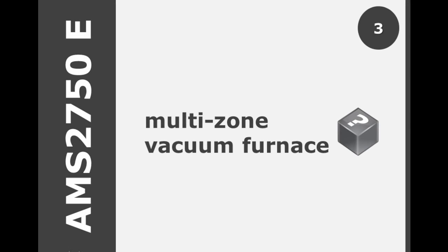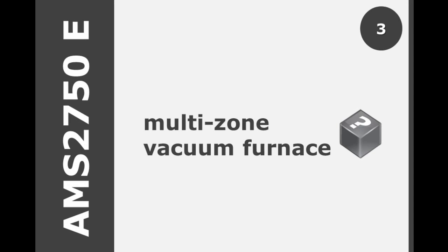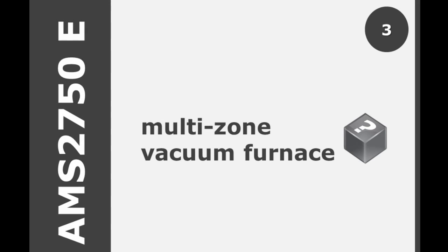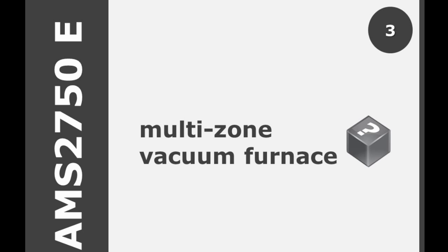In E, rather than applying this to each control zone, you can split the entire working volume into 225 cubic foot zones and treat each of these zones as a single control zone to determine the overall number of high, low, and load sensors.